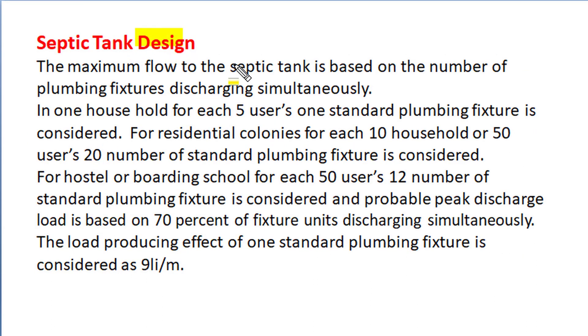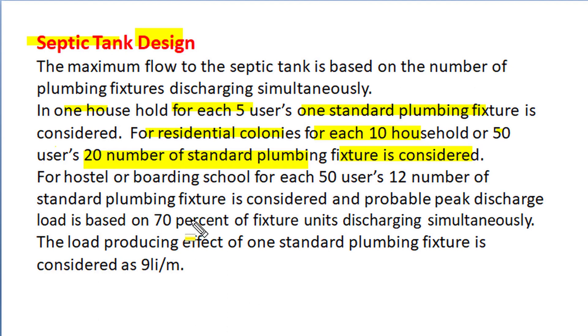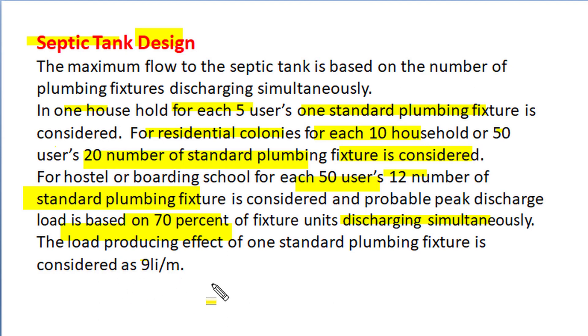The maximum flow to the septic tank is based on the number of plumbing fixtures discharging simultaneously into the septic tank. For one household, for each 5 users, one standard plumbing fixture is considered. For a residential colony, for each 10 households or 50 users, 20 number of standard plumbing fixtures is considered. For hostel or boarding schools, for each 50 users, 12 number of standard plumbing fixtures is considered with diversity in application. Probable peak discharge load is based on 70% of fixture numbers which will discharge simultaneously, and for each standard plumbing fixture, the load producing effect is considered as 9 litres per minute or 540 litres per hour.